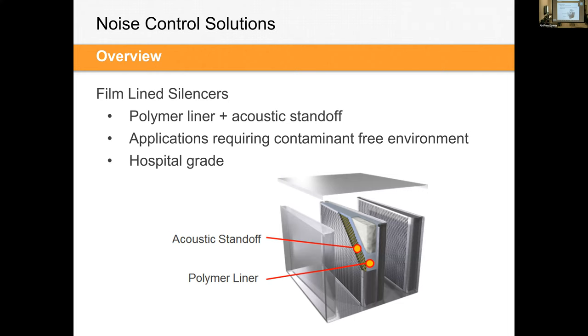One thing that we do at Price as standard is we always offer this acoustic standoff, which is a thin acoustical spacer that goes between the perforated metal and that polymer film. And it works very well for increasing the insertion loss or sound absorption of the silencer. When you don't have that in place, the polymer film often just sucks up against the perforated metal and sound will propagate through it very easily. So it's a great option, and we do it on every polymer film liner. It's not an option. It comes standard.